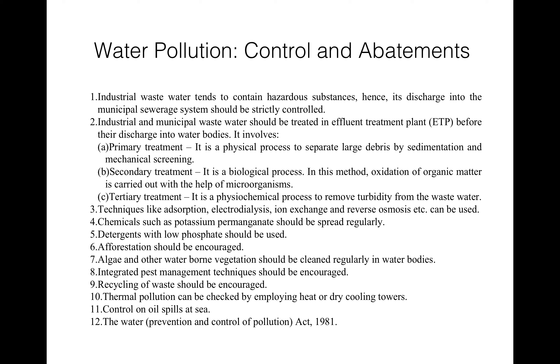The third is tertiary treatment — it is a physicochemical process that removes turbidity from wastewater. Oxidation of wastewater is done by strong oxidizing agents like chlorine, perchlorate salts, ozone and UV rays. Additional techniques like adsorption, electrodialysis, ion exchange method and reverse osmosis are also used for removal of biological, chemical and radioactive water pollution. Chemicals like lime and ferric chloride are spread regularly to protect water from microorganisms and to precipitate phosphates.